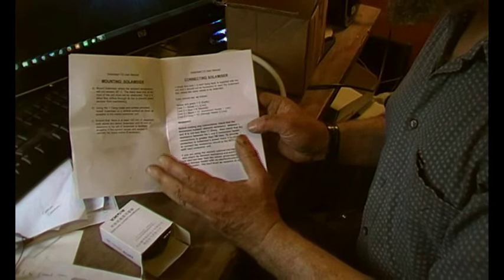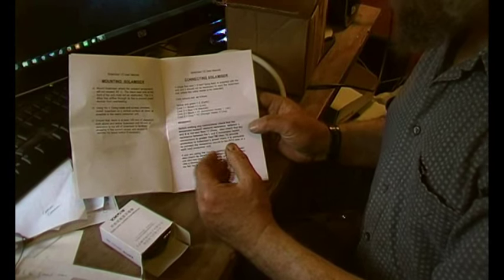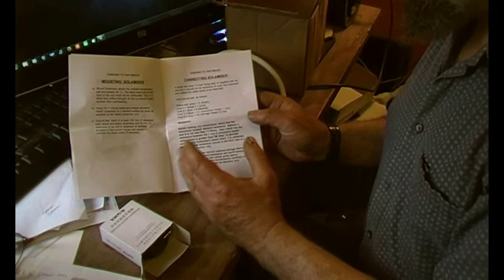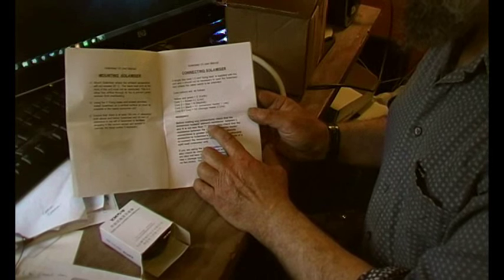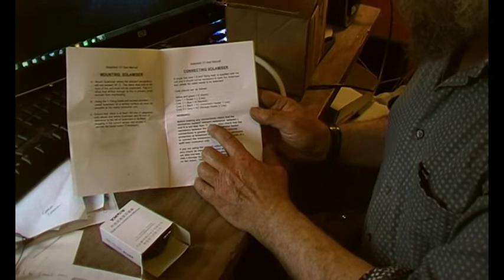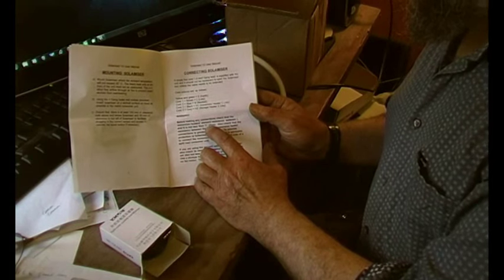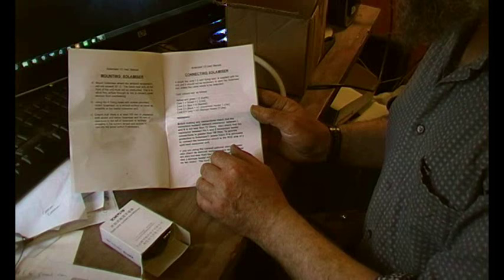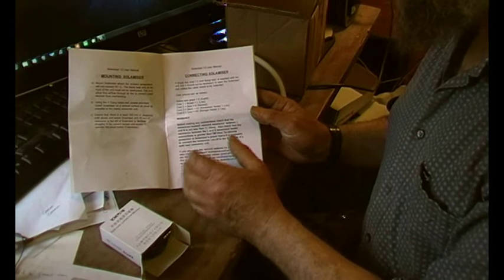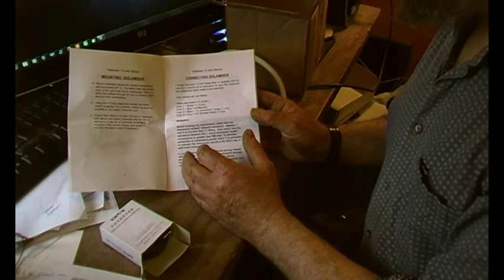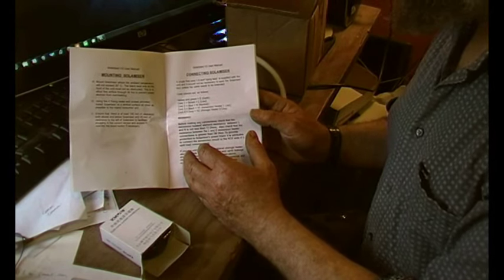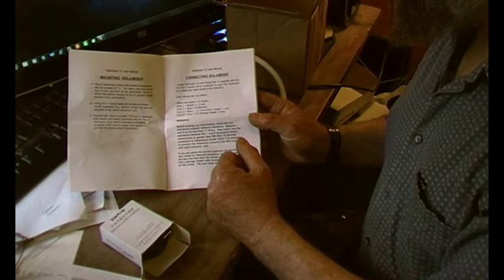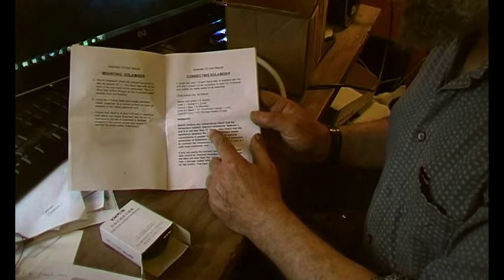The main thing is disconnect and switch off from the mains. Make sure everything is switched off. Then you have to check the resistance of the immersion heater circuit. Now of course, although it's disconnected from the mains, you've still got to have the immersion heater switched on, although there's no power going through it. And make sure that the thermostat hasn't switched itself off, because if it switches itself there'll be no circuit.